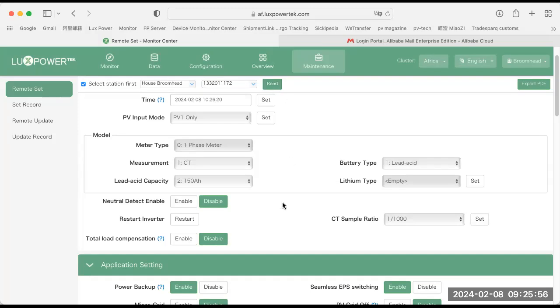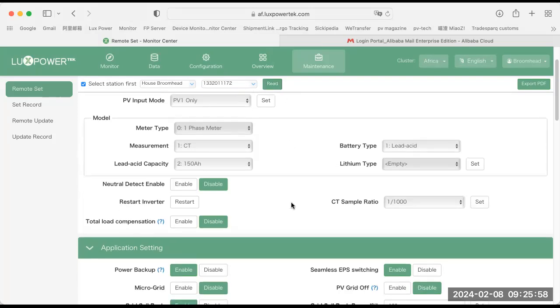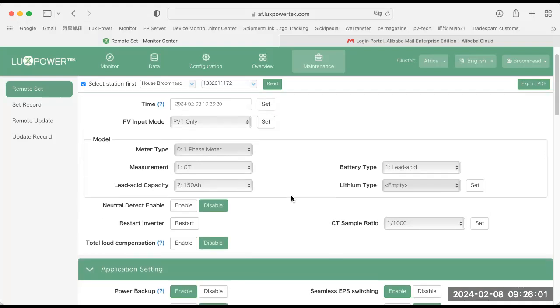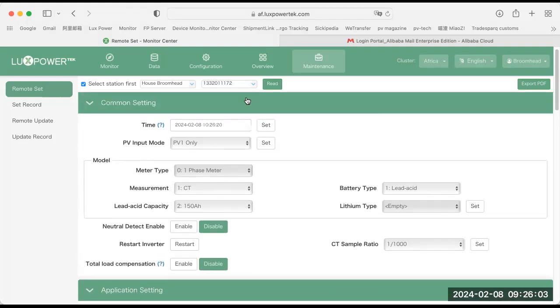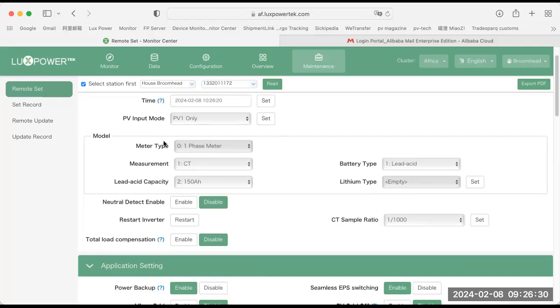So, on the remote settings page, I'm going to focus on what we spoke about last week, particularly this block here, the time block. The time block is determined when you set up your station originally and register the dongle: you select the region and the time zone. That is the time that will go in here. Make sure that you also uncheck daylight saving, especially in South Africa. We do not have daylight saving, so you have to uncheck that so that you get accurate times. All right. Standard, we have CT metering.